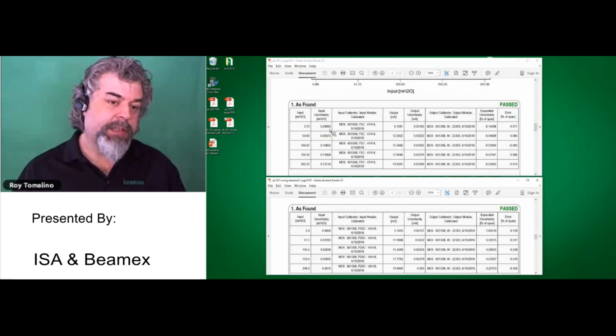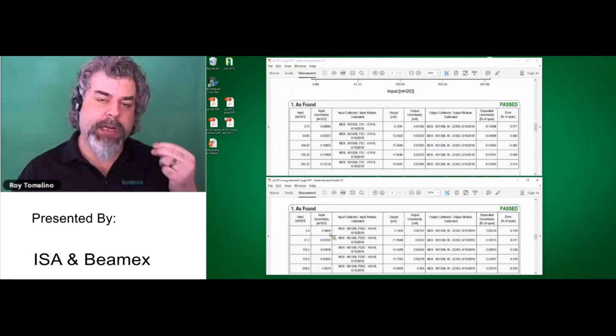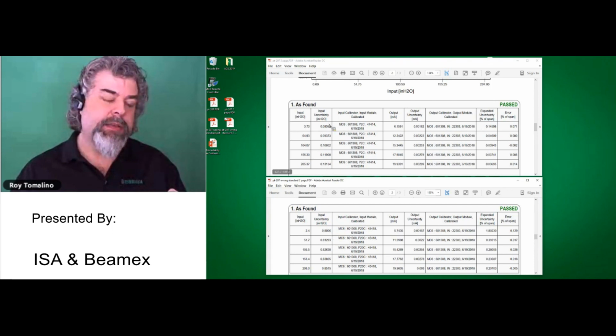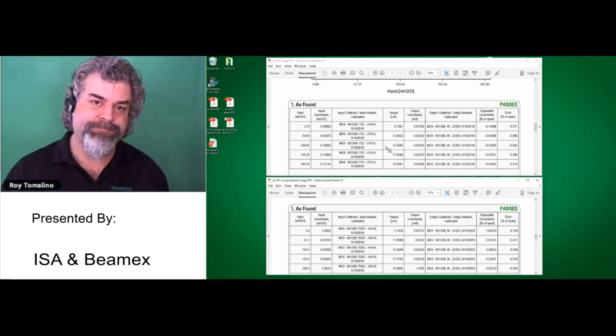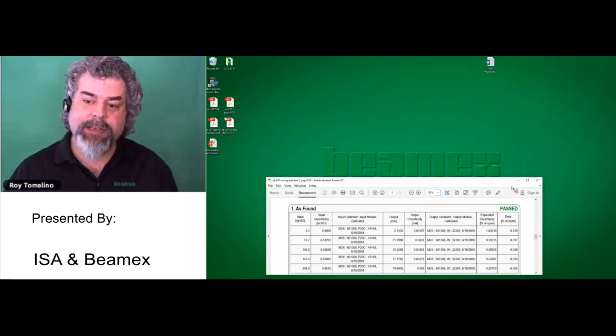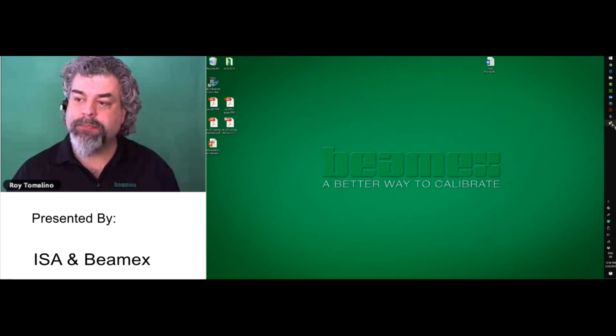The input uncertainty on the very first one, on the bad one down here, 0.8 inches of water is our uncertainty on the input. The input on the better test, the better uncertainty, is 0.08. That's a factor of 10. So we're 10 times better on the uncertainty on our 30 PSI module. And with that, I'm done with the second live demo.